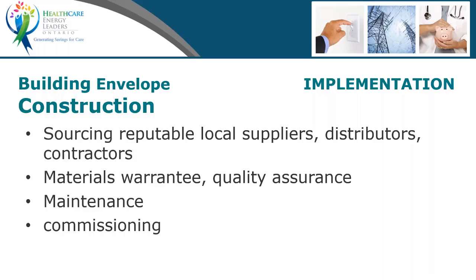Commissioning is a big thing too, getting it commissioned right. I went to a conference a couple of years ago, and I think it's about 25-30% of commissioning finds fault in the design and installation of systems from their original intention. So good commissioning by independent experts in air balancing, getting the right equipment and the right filters, matters. We've all seen valves installed the wrong way, dampers facing the wrong way, louvers that don't function. So to get commissioning right in the first place, you get about a 75% chance of having it right.